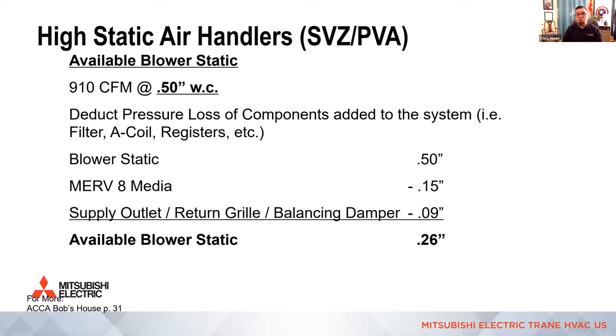All right. Great question, though. So we have a 0.15 pressure loss because we're moving more air through the same size filter compared to the lower volume of air through the same size filter on a lower static. So 0.15 subtracted from what we started with, 0.50. And then, of course, one supply register, one return grill, and a balancing damper. So 0.03 a piece. Remember, this is not a stock list. It's just the longest run. We deduct that from what we started with, and now we end up with 0.26 for the top side of the equation.